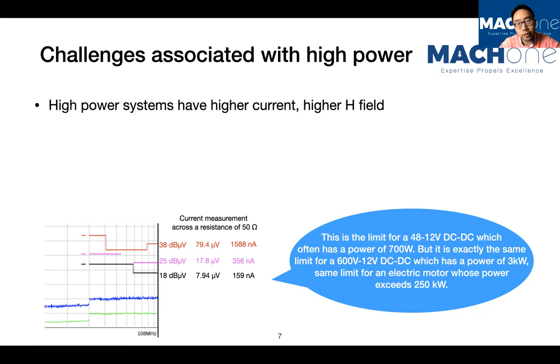Another thing is that a high power system has to bear in mind it shares exactly the same noise limit value as a low power system. For instance, here we demonstrate the CISPR 25 Class 5 conducted emission limit, with values relating to peak, quasi-peak, and average.